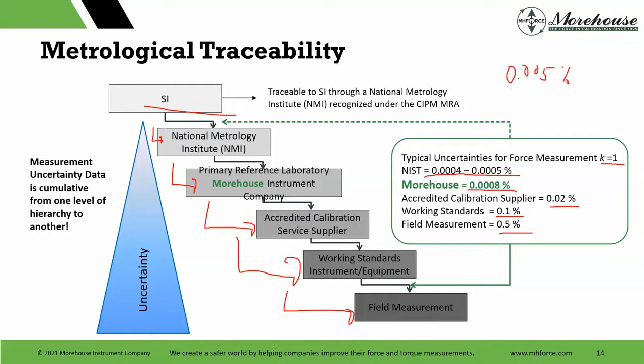But then, the National Metrology Institute calibrated our standards. We calibrate them as a primary lab for accredited suppliers, working standards. And as you can see, if we keep going, the uncertainties get larger each step. And the important part of this is you cannot, and people do this, believe it or not, you cannot have an uncertainty lower than the lab that did the calibration. So if you have a super ultra piece of equipment, someone says it's good to 0.005. You send it to a lab that's at 0.01, your starting point now has got to be worse than 0.01. So we'll talk about that as this moves on.